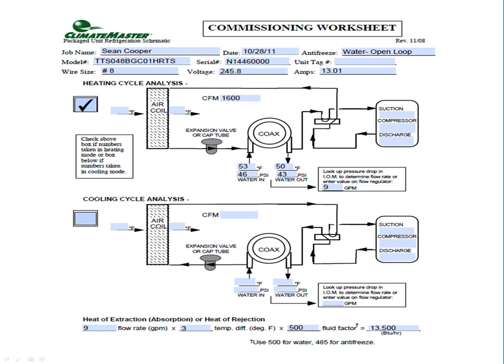So, for example, this form, in my opinion, can be the commissioning or startup form, should be, as well as it can also be a troubleshooting form initially when you go out to see what's going on, even if it's just routine maintenance. Always perform this. Take the voltage, make note of the amps draw, make note of the wire size serving it. So you're going to see in this example, you have boxes near the air coil that you can check so that you can reference, look, I checked this in the heating or in the cooling cycle. In this case, just above the coax, behind the air coil, we have a place where you can record your CFM. Remember, you counted 1 blink per 100 CFM.